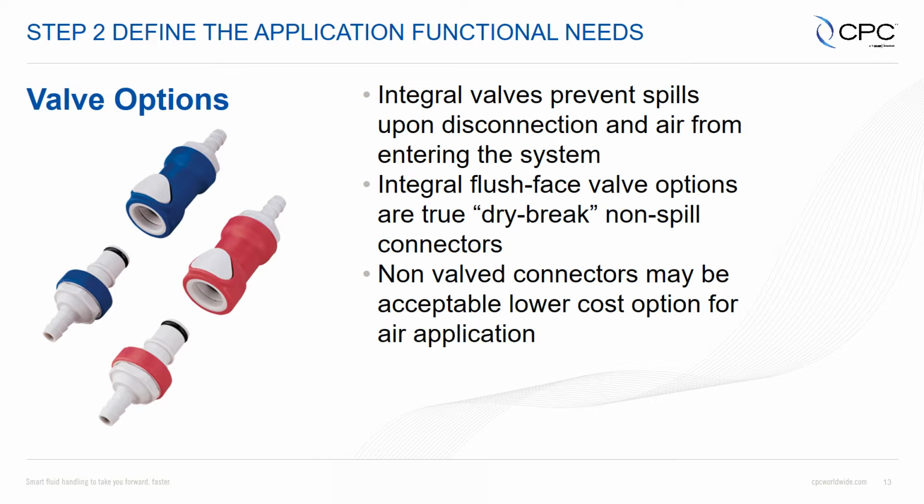Now, if you're in low pressure air or particularly in gases, we see a lot of customers using non-valved connectors. It provides a lower cost option. It's a simpler part because we're removing features, we're removing the valve from the inside. So valved or non-valved or whatever style, CPC can work with you to select the right valve option for your application.